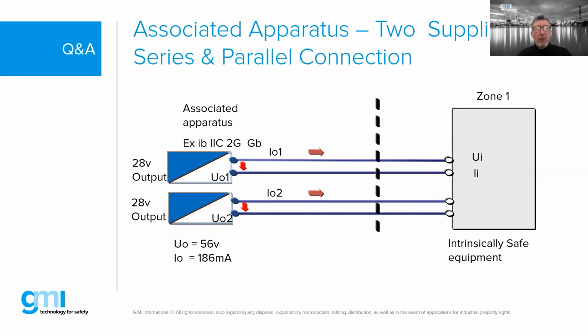While we're at it, maybe we should explain something, since there was a question earlier about how an associated apparatus, the barrier, and the field device or intrinsically safe device need to match. The question was, if I have an IS device which is safe in the hazardous location, why do I need a barrier? So if you look at it, we didn't really talk about this, but there's a difference between a simple device and a certified device.